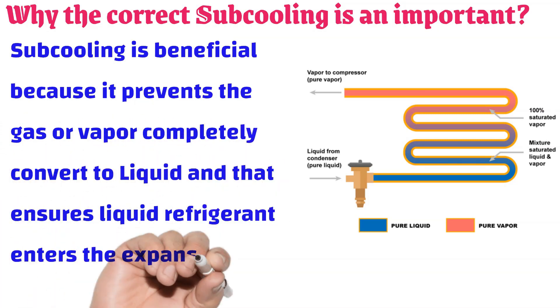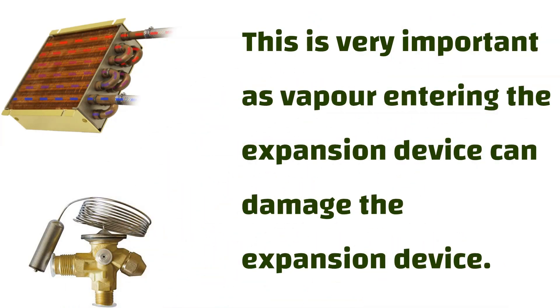Why is correct sub-cooling important? Sub-cooling is beneficial because it prevents gas or vapor and ensures the vapor is completely converted to liquid, ensuring liquid refrigerant enters the expansion device. This is very important, as vapor entering the expansion device can damage it.